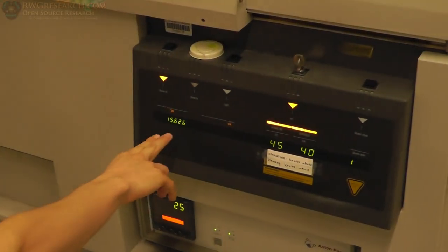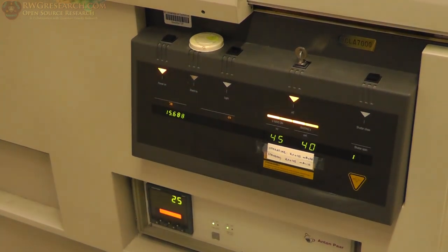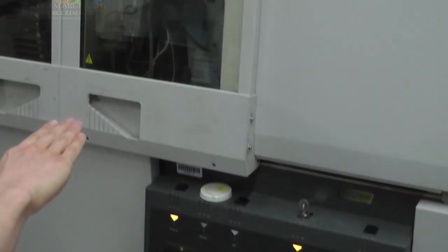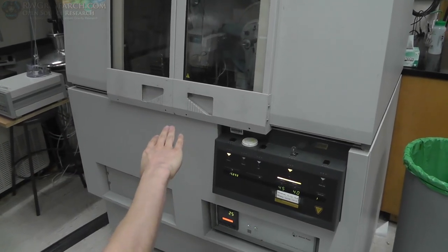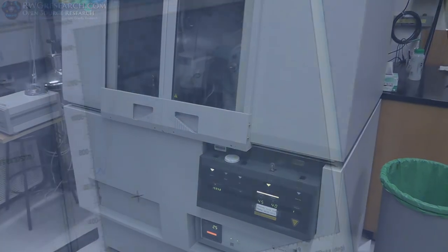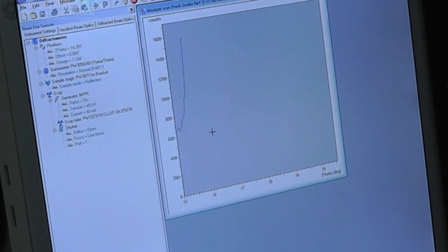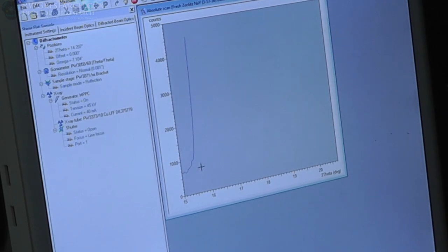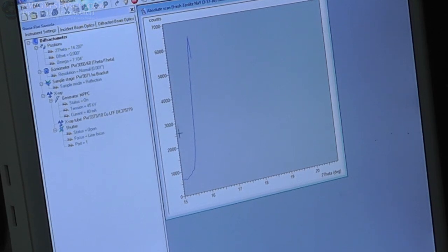So here it shows the actual degrees and two theta that it's at. And so you can actually, you can't really see because of how slow it's moving, but it's very slowly increasing. Right now it's at like almost 16 degrees two theta. So we're actually getting a peak right now, it looks like, right away. So can you explain to me what we're looking at here? Yeah. So what this shows you, two theta degrees. So it's the angle on the bottom. Yeah. And this is the count. Mm-hmm. So this is the intensity. So right now, we just encountered like our first peak.